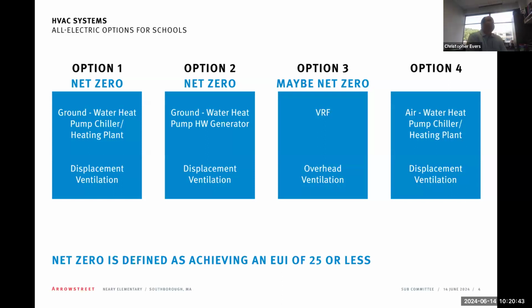And it kind of depends on the location. On some projects, even if there is gas on the site, you cannot get a new hookup. Most of the utilities won't allow you to use gas in your building if it's not the prime source of heating. So option one obviously is going to be our most expensive, because we would have to put a well field out and drill wells.